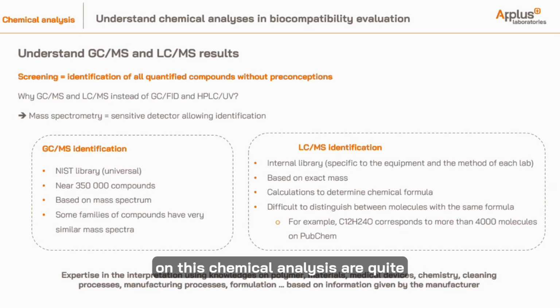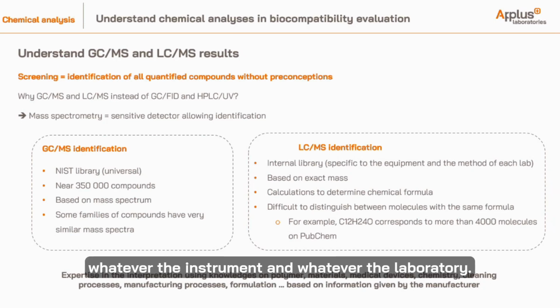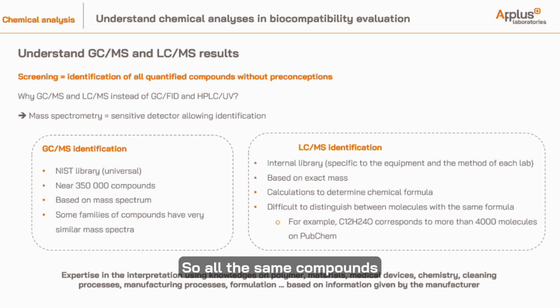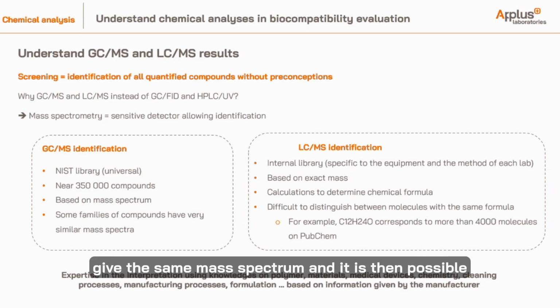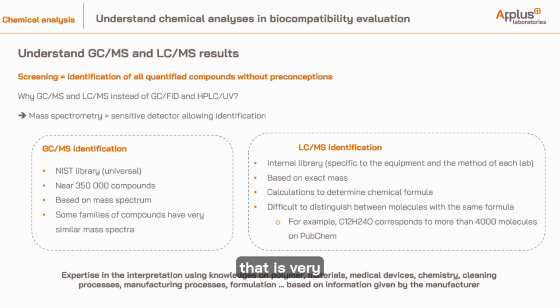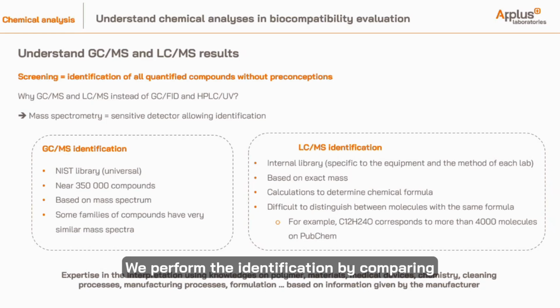The identification of compounds based on this chemical analysis is quite different depending on the technique. For GC-MS results, we have a universal library such as the NIST library, because this equipment will lead to the same result, whatever the instrument and whatever the laboratory. So the same compound analyzed everywhere in the world will give the same mass spectrum, and it is then possible to have a database that is very large, because this library has 350,000 compounds. We perform the identification by comparing the mass spectrum obtained in the chromatogram of the medical device extract to the library, and see if we have a similar spectrum with one or more compounds.